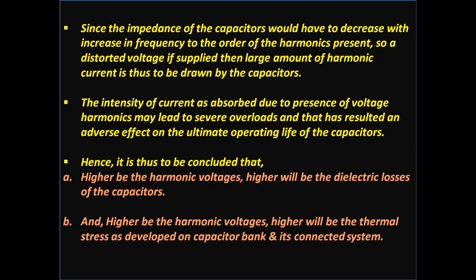It is thus concluded that: number one, higher the harmonic voltages, higher will be the dielectric losses of the capacitors; and number two, higher the harmonic voltages, higher will be the thermal stress developed on the capacitor bank and its associated connected system.